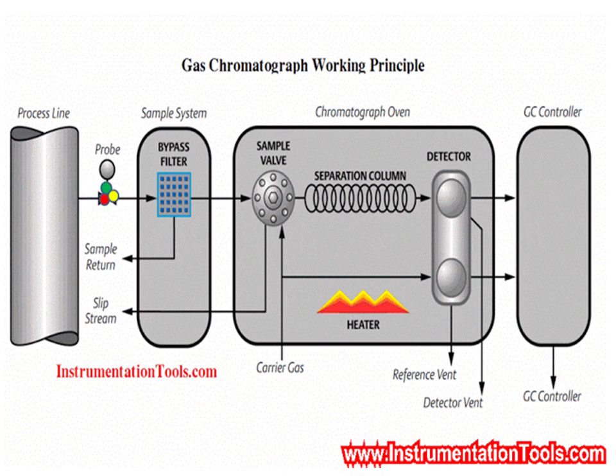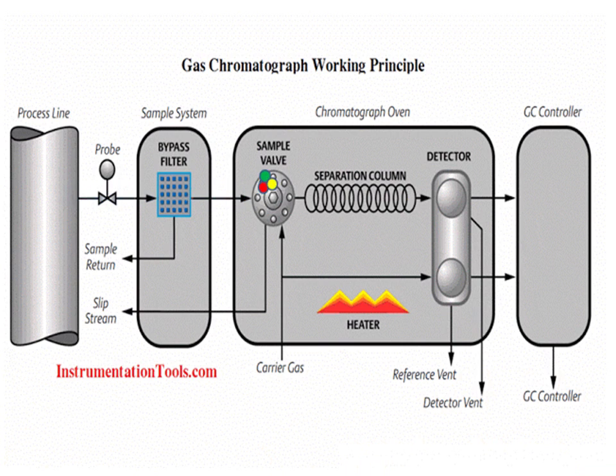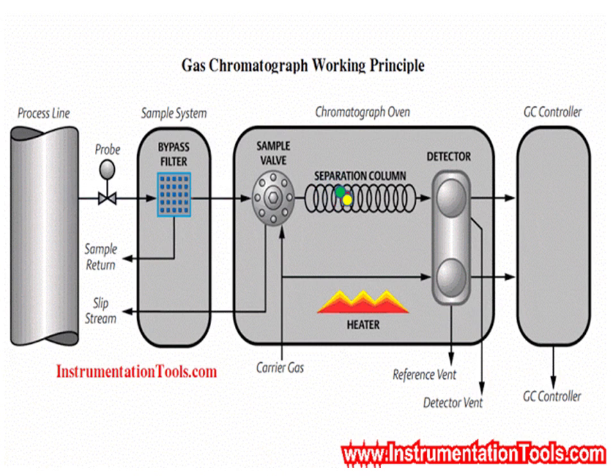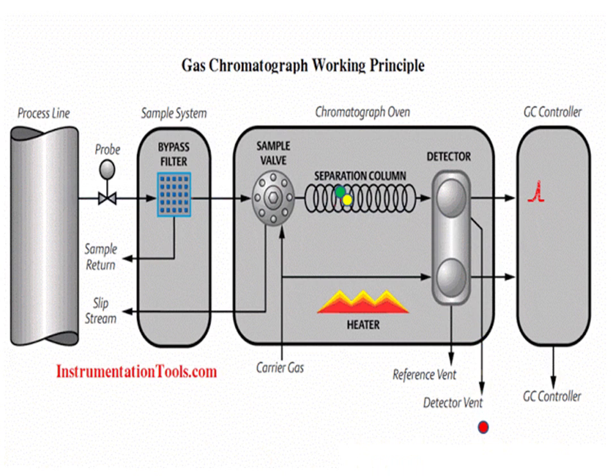GC working principle briefly. The sample gas will be taken from the process pipeline through the GC sampling system. A carrier gas, generally helium, will be used to carry the collected sample gas through the GC column.